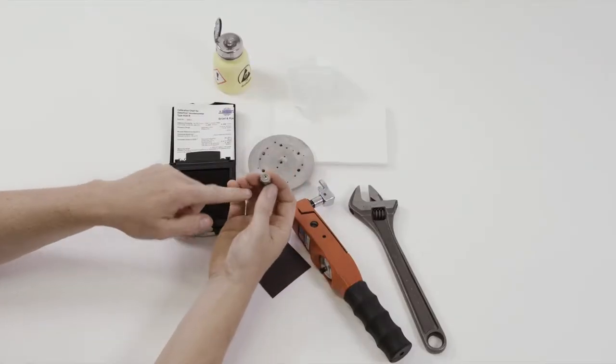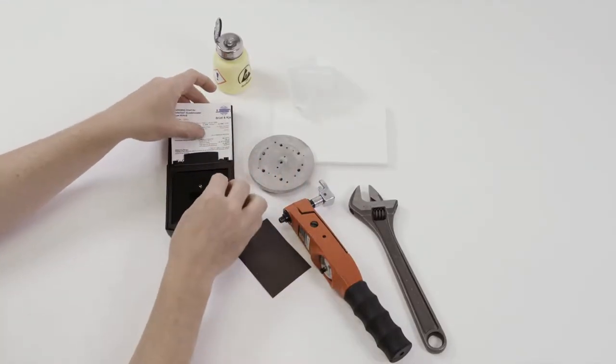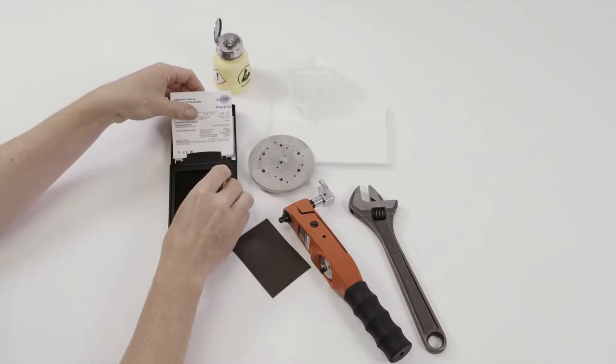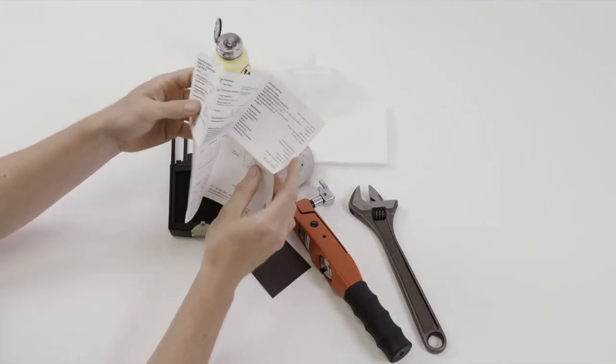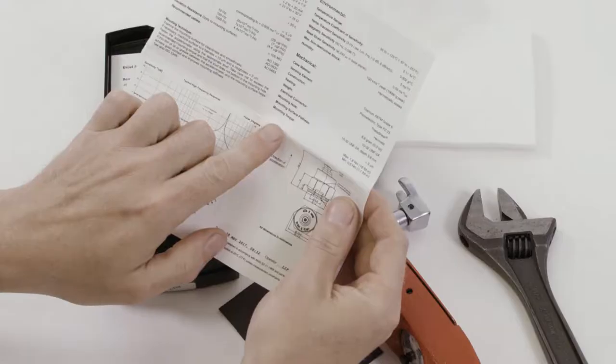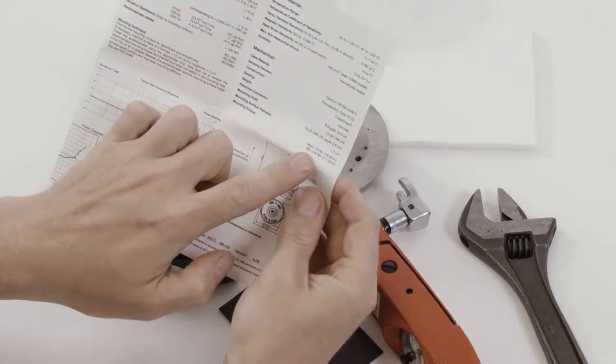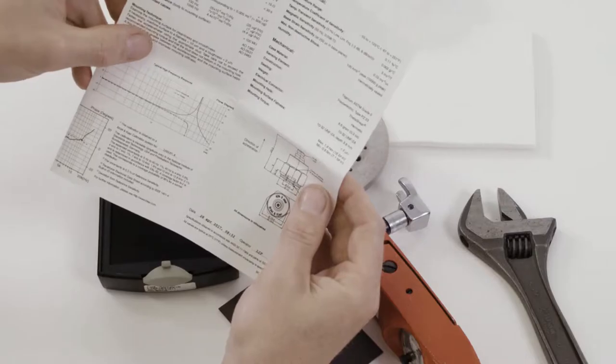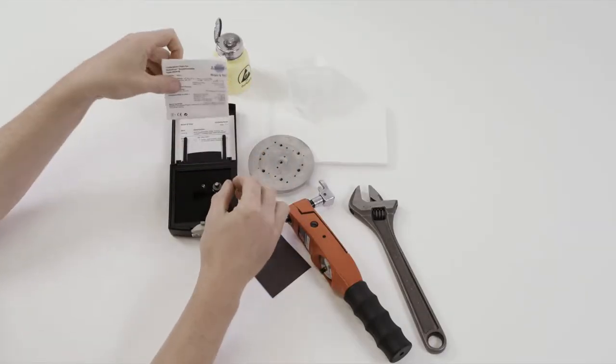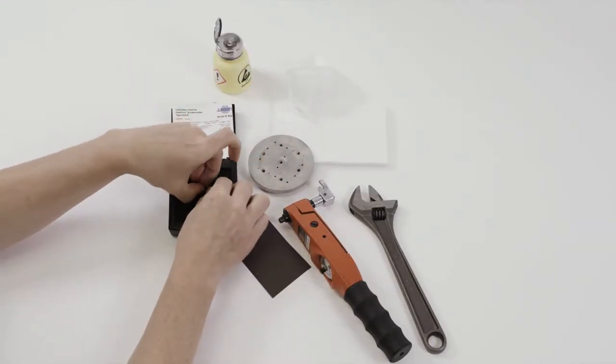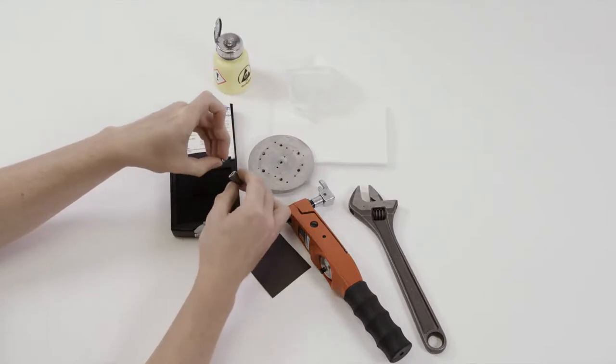For a stud-mounted accelerometer like 4534B, we have a specification for mounting torque on the calibration chart. Here a range between 0.8 and 1.8 Nm. When stud-mounting the accelerometer by using, for example, the supplied threaded stud into a threaded hole on a supporting structure.